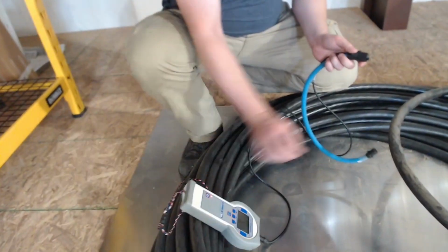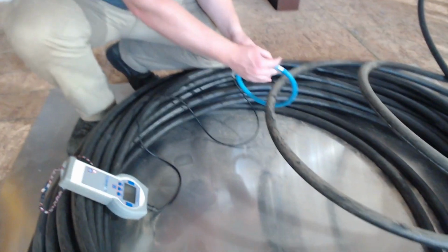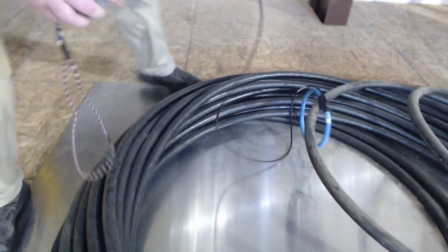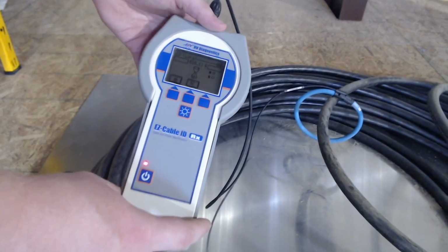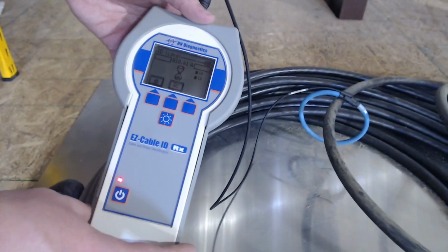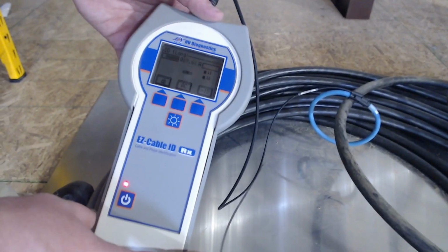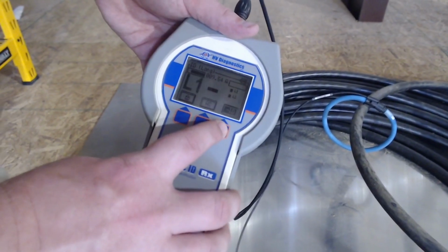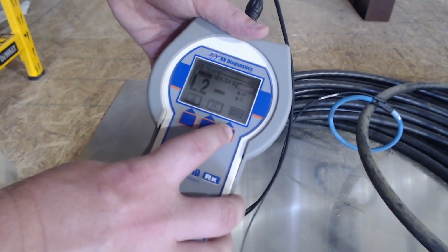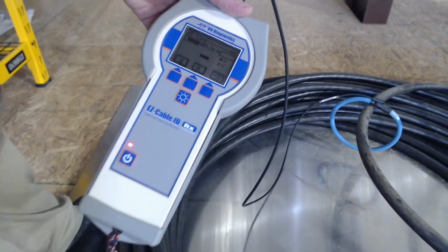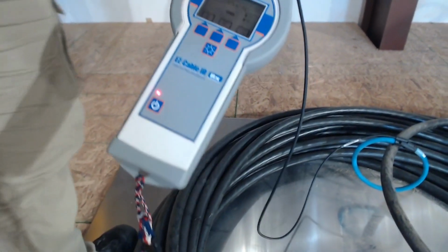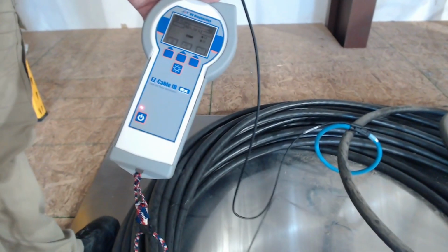Once we hook on and it identifies, if I have the coil the right way, we should get a negative. And if we hit ID, L1, hit ID again, L2. So this verifies that both of our unique signals are now coming down on our return of our C phase. So now we have successfully identified all three phases.